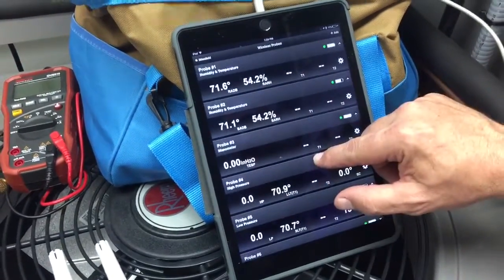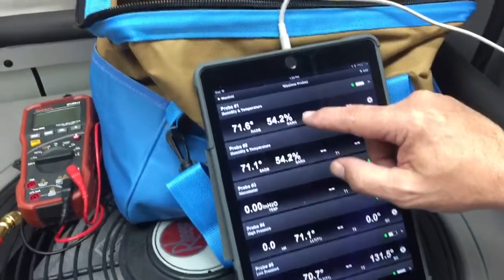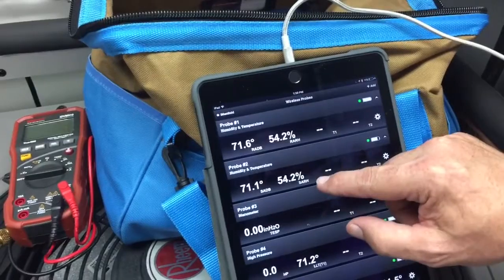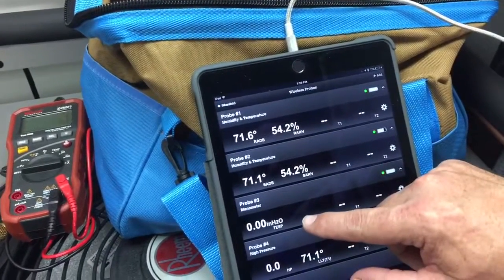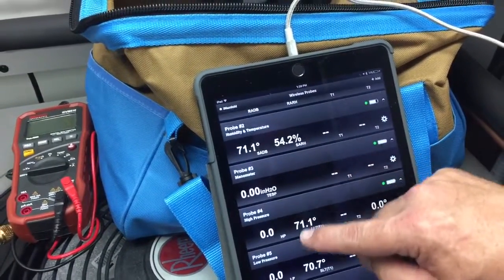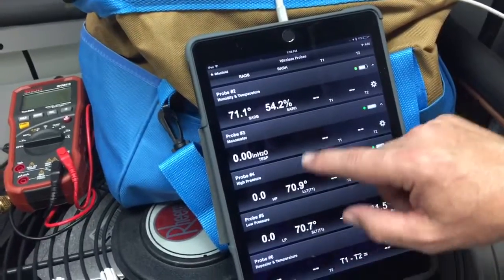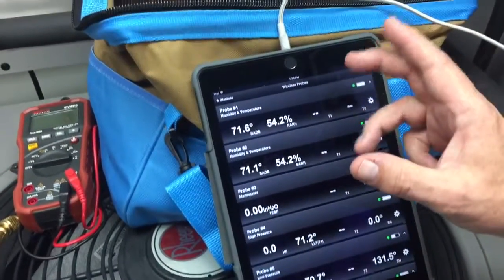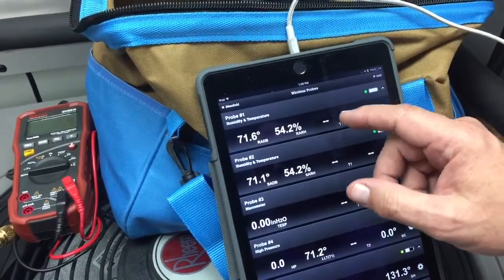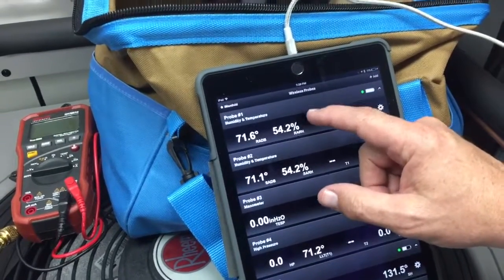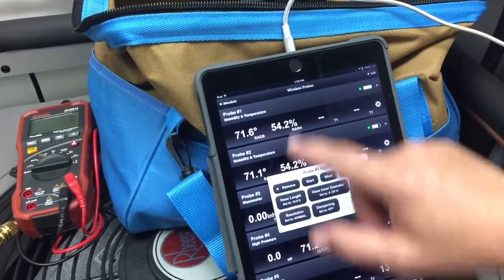By default, we mapped them all for you. You can see the first probe is your return air, the second probe is your supply air, the third probe is your total external static pressure, then our high pressure probe, our low pressure probe, and our repeater. Now, let's say we want to change them. Maybe I want my first probe to actually be supply air. All I do is tap on the subscript. Oops, I tapped on the gear by accident with my knuckle.